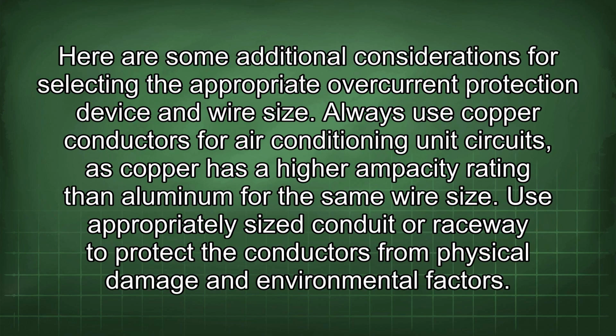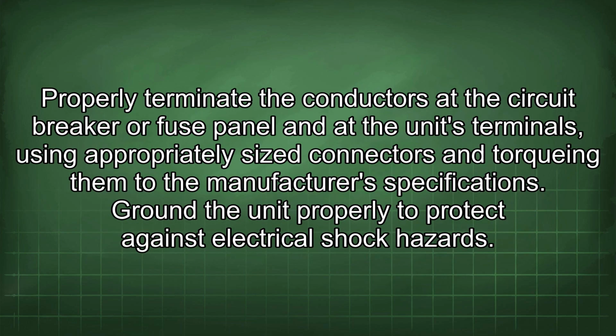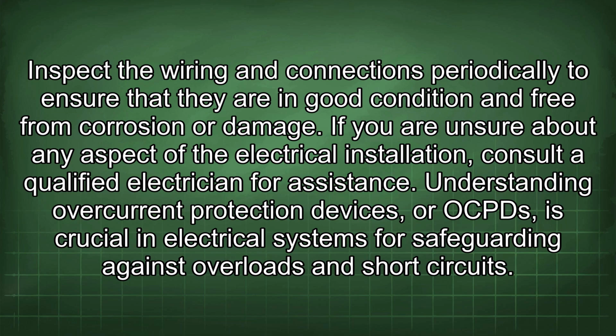Here are some additional considerations for selecting the appropriate overcurrent protection device and wire size. Always use copper conductors for air conditioning unit circuits, as copper has a higher ampacity rating than aluminum for the same wire size. Use appropriately sized conduit or raceway to protect the conductors from physical damage and environmental factors. Properly terminate the conductors at the circuit breaker or fuse panel and at the unit's terminals, using appropriately sized connectors and torquing them to the manufacturer's specifications. Ground the unit properly to protect against electrical shock hazards. Inspect the wiring and connections periodically to ensure that they are in good condition and free from corrosion or damage. If you are unsure about any aspect of the electrical installation, consult a qualified electrician for assistance.